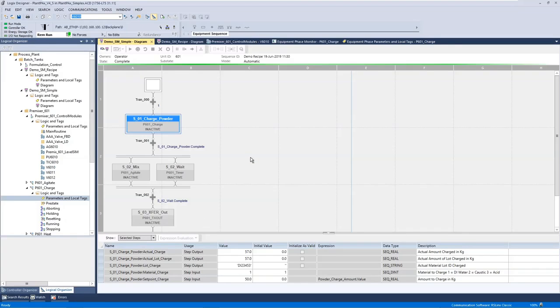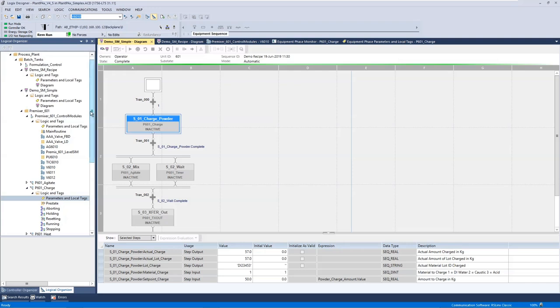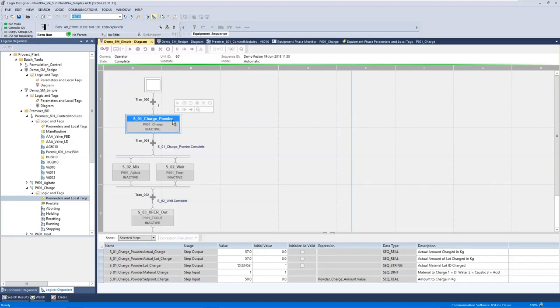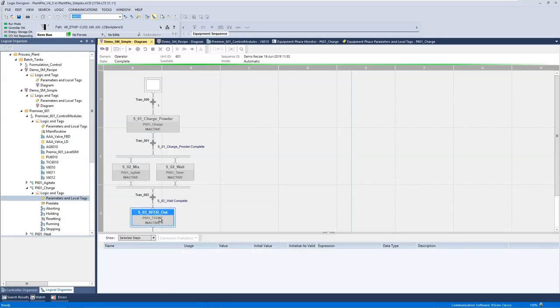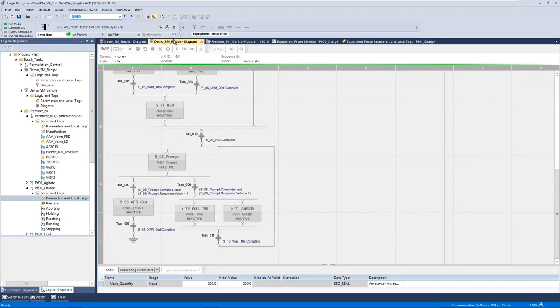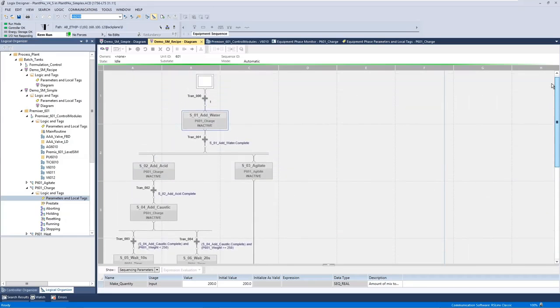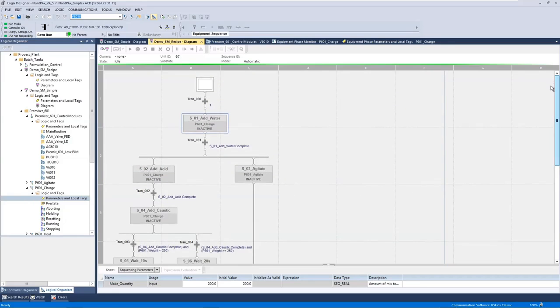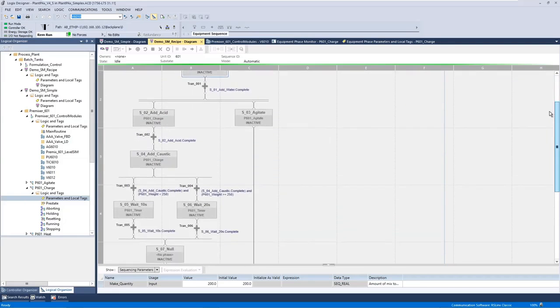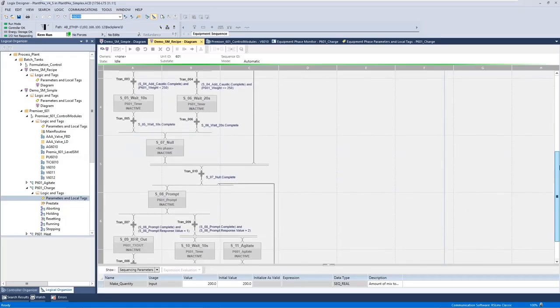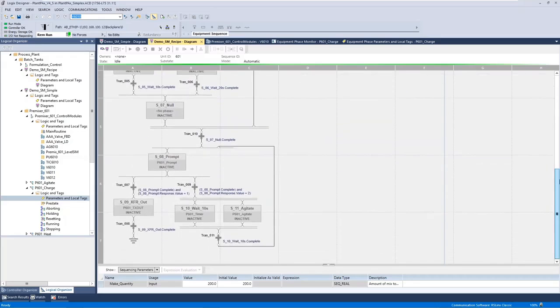To execute Sequence Manager, you need to use equipment phases. You can then write as many Sequence Manager sequences as you can fit into the controller memory in your controller, and there you can select any of the equipment phases that you have in your controller. You can run a simple type of recipe like you see here, where we run a single equipment phase, we run equipment phases in parallel, then we go back to single, or you can go to more complicated recipes where you can run those phases in parallel, and you can have loops as well if you wish, or diversions where you go from one route or another.